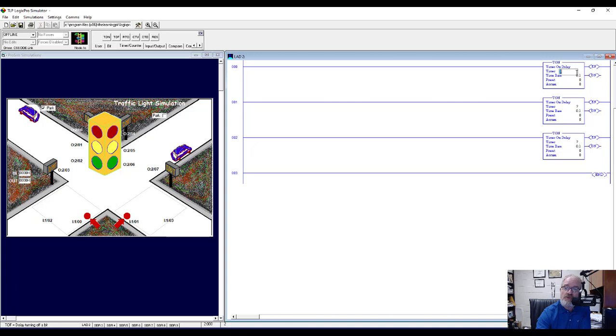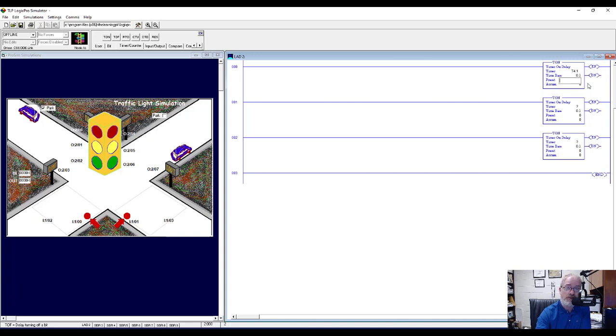Let's give them addresses. The first one I'll double-click and type T4:1 and hit enter. Now that it has an address I can put in a preset value. The preset value isn't exactly the time in seconds because the time base is 0.1. So to get 12 seconds we need to put in 120, because 120 times 0.1 equals 12. So 120 is the preset for the first timer.